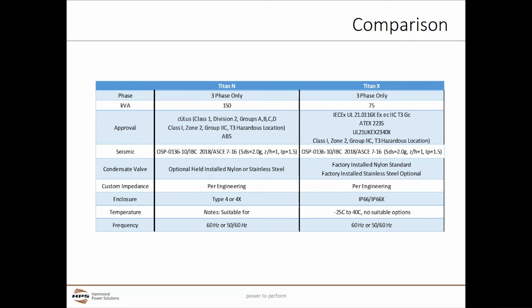One of the biggest differences in regards to the approval between Titan N and Titan X is that IEC approvals or certificates require us to put the ambient temperature rating on the actual nameplate. For Titan X, the temperature rating is between minus 25 to 40 degrees C. Titan N is a similar ambient temperature, but depending on the rise of the unit, we are able to put suitable for a different temperature rating if it is a higher or lower temperature rise unit. Both Titan N and Titan X are offered at either 60 Hertz or 50-60 Hertz.